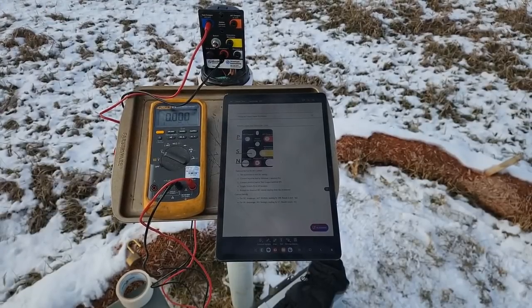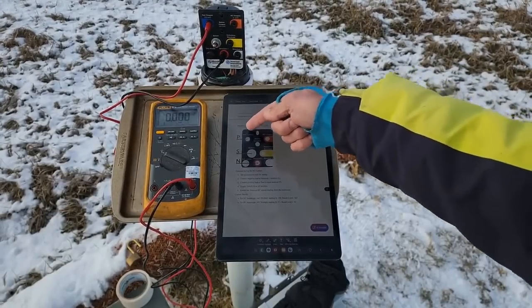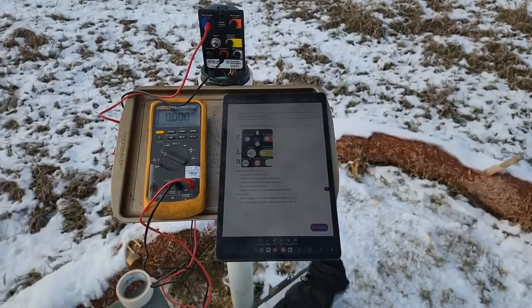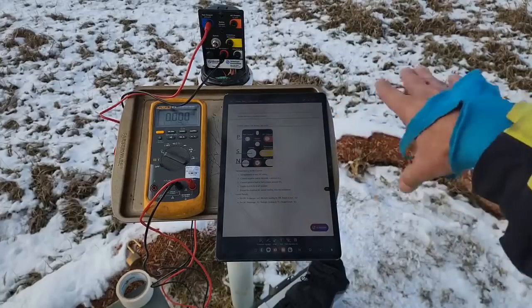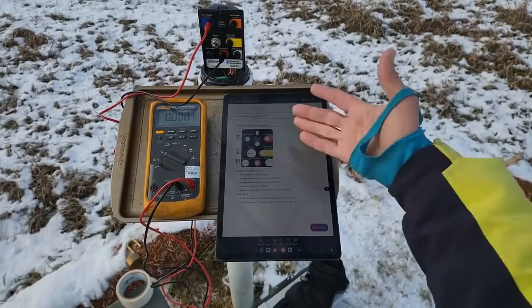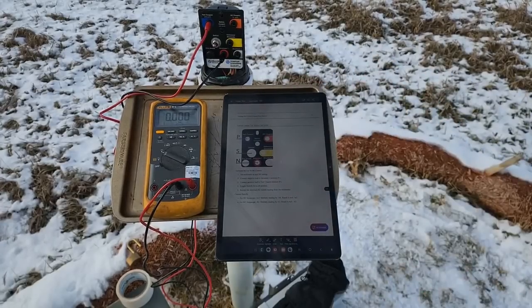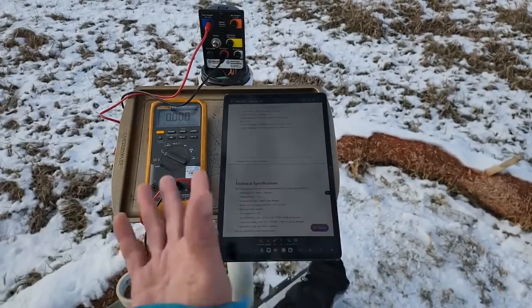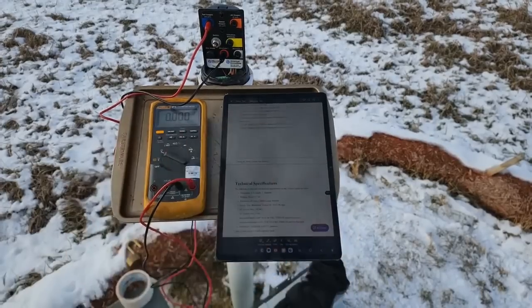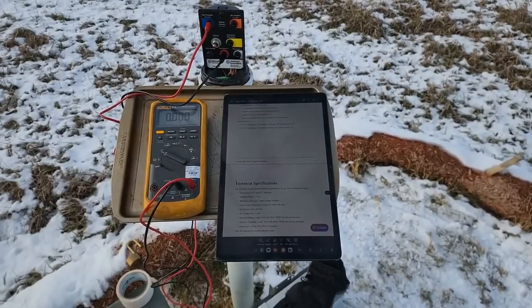Because if the value comes out positive, it means that the current is entering behind the coupon and going towards the pipe. And that's what I want to see. This means that the cathodic protection is in the environment surrounding the coupon, and that current is entering the pipe, and that's what we want. Well, basically, this is what the manufacturer tells us about how to take measurements on the coupons and how we should connect them.